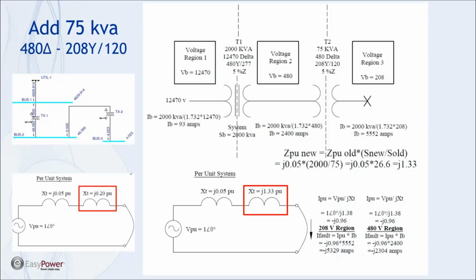My motivation for this is to understand how smaller transformers impact available fault current. That is certainly an option you can use if you break a system up. You have the expense of more transformers if you want to completely utilize your system capacity, and I have not done an economic analysis of what we're discussing here. From a safety standpoint, it makes a lot of sense to incorporate these transformers to reduce the available fault current. But the flip side is it does add impedance to the system, which contributes to voltage drop in the system. So there are trade-offs that you have to look at.